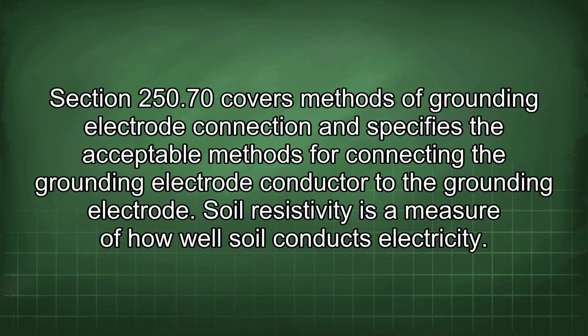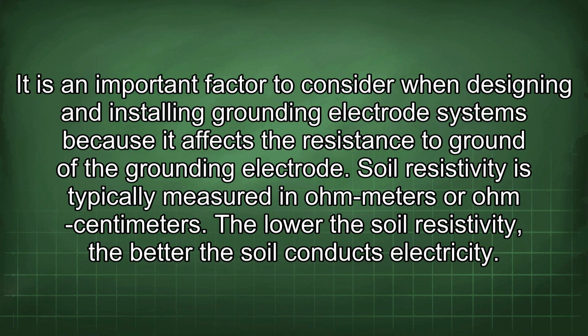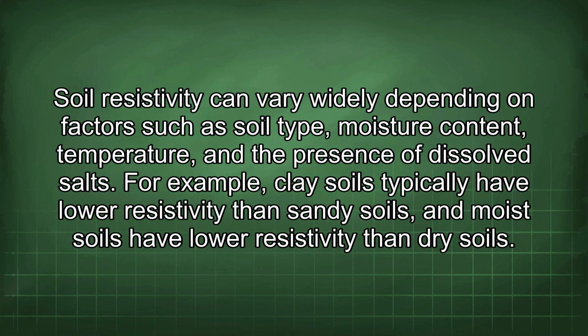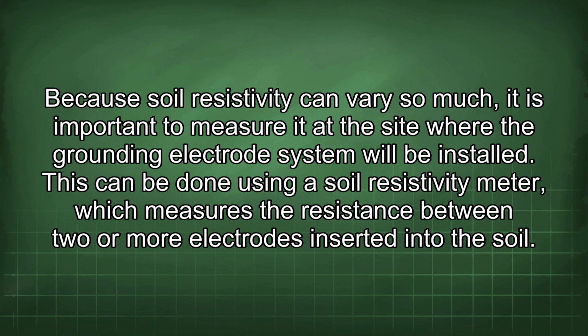Soil resistivity is a measure of how well soil conducts electricity. It is an important factor to consider when designing and installing grounding electrode systems because it affects the resistance to ground of the grounding electrode. Soil resistivity is typically measured in ohm meters or ohm centimeters. The lower the soil resistivity, the better the soil conducts electricity. Soil resistivity can vary widely depending on factors such as soil type, moisture content, temperature, and the presence of dissolved salts. For example, clay soils typically have lower resistivity than sandy soils, and moist soils have lower resistivity than dry soils. Because soil resistivity can vary so much, it is important to measure it at the site where the grounding electrode system will be installed.